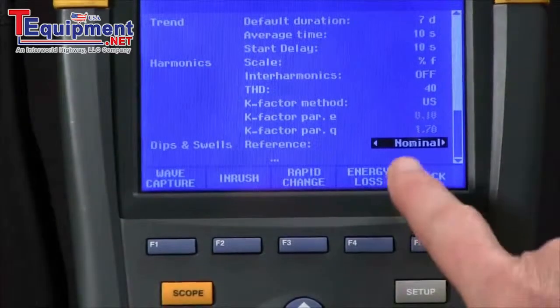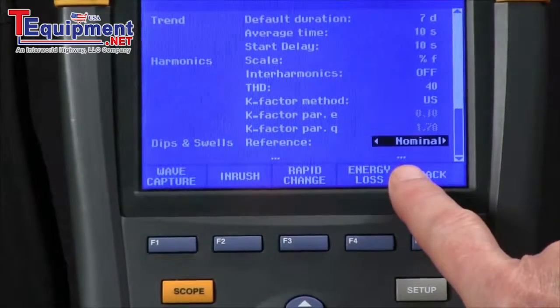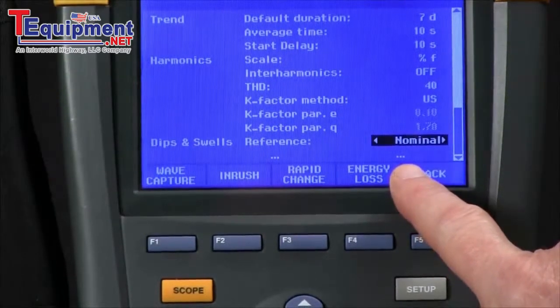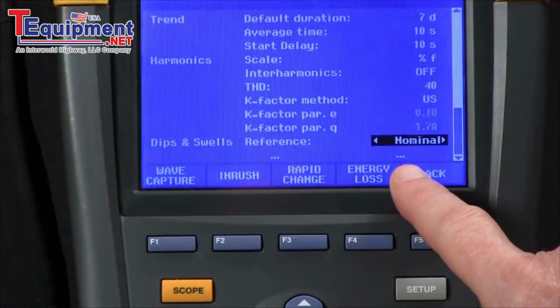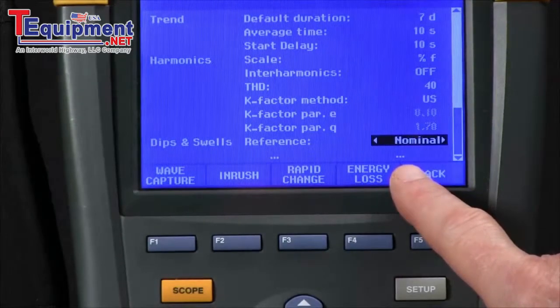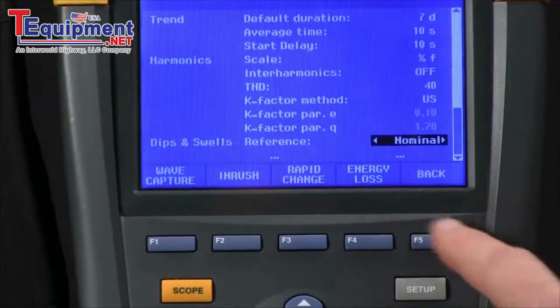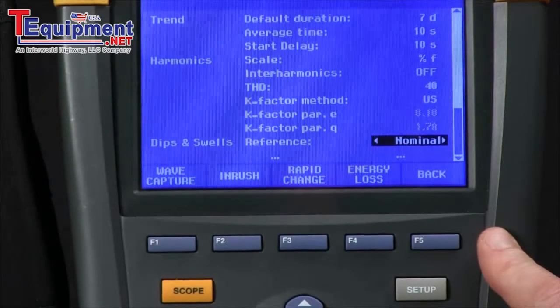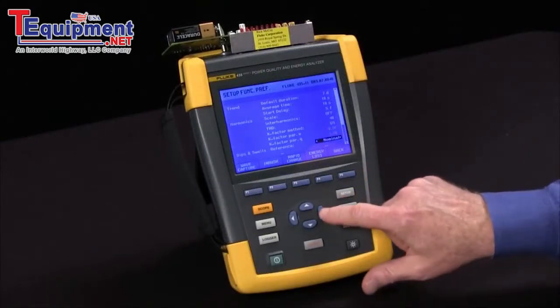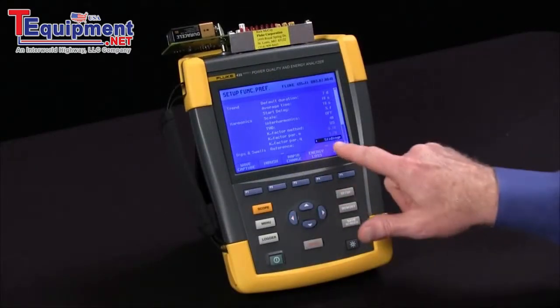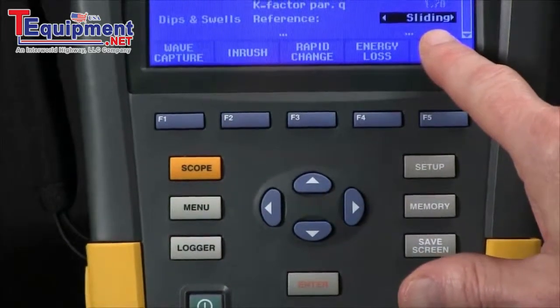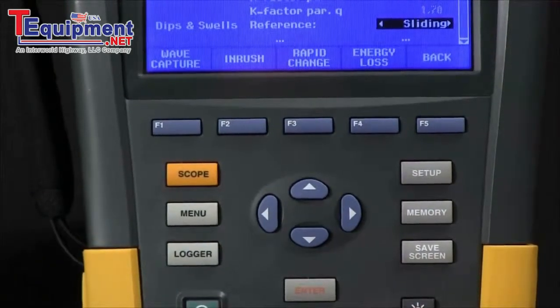Right now it says nominal for that, which means our reference voltage is the 120 volts we selected in our main setup. But if your voltage isn't really 120 volts — it's 115 or 110 — and we want the actual voltage to be the reference, we use the arrow key to select sliding.